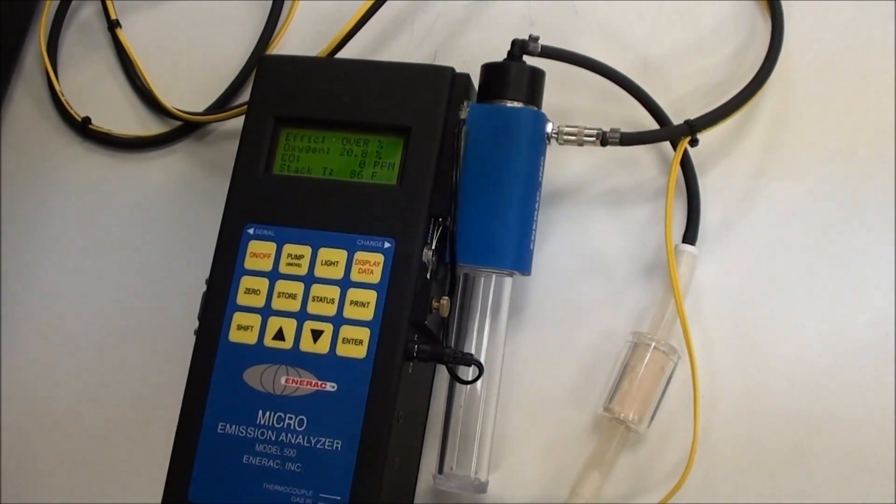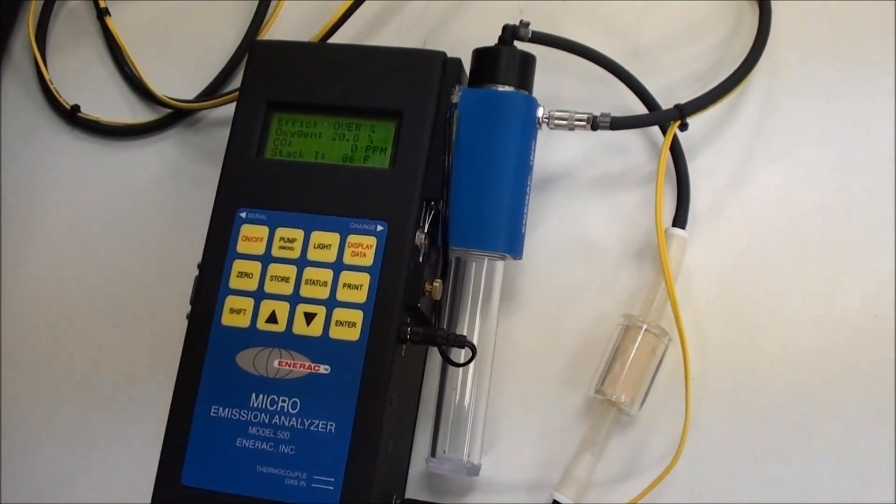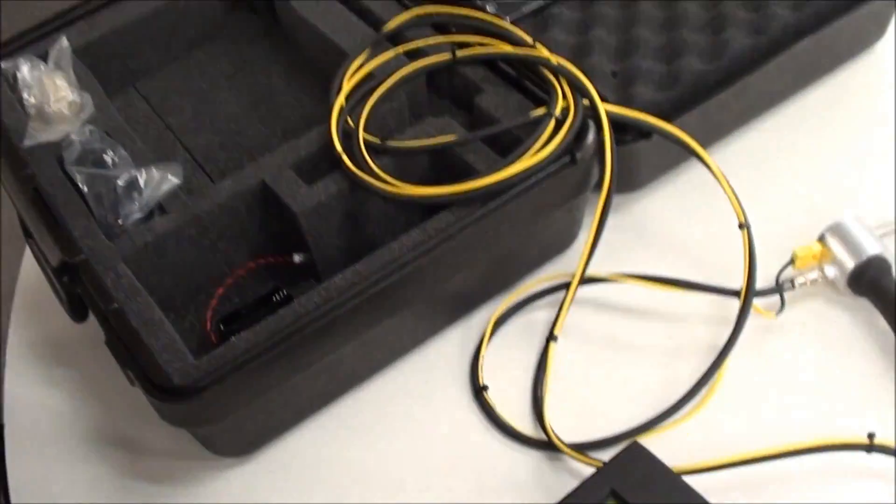Oxygen will read 20.8, 20.9. All the other sensors should read zero. The stack temperature should read what the ambient temperature is. So when you're finished, your stack temperature reading gives you gross stack, not net stack temperature. It includes the ambient temperature in the reading, so keep that in mind.